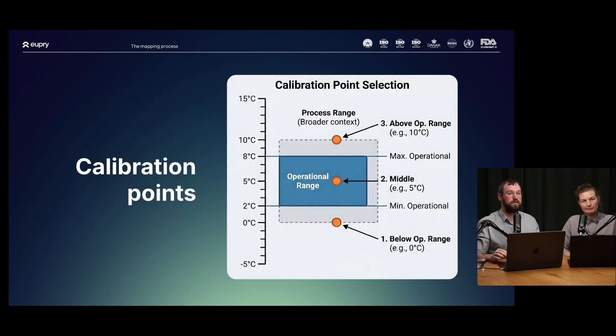So first of all, how should you set your calibration points? The important thing is that you have an operational range, let's say 2 to 8 degrees, but you need to have calibration points that are outside of this range, because what happens if the temperature goes just a little bit outside these points? You'd still want to have your calibration to be valid. And why do you need those calibration points?